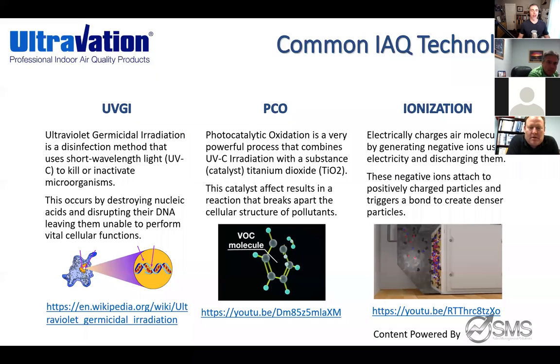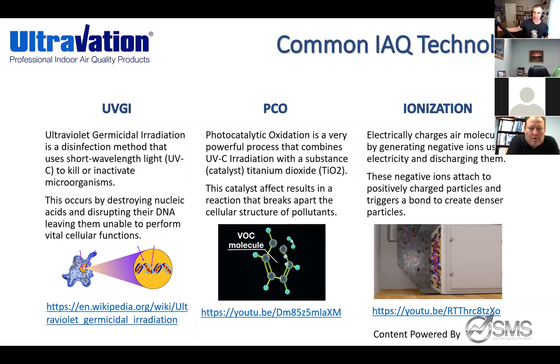It doesn't matter whether titanium dioxide is on a metal surface or infused into carbon. Photocatalytic oxidation is not possible without the UVC lamp. If you're using carbon, that's better because it removes any ozone smell — the carbon absorbs it. That's what Dan and I were working on: bringing in products that have the ability to give you a zero-ozone offering.